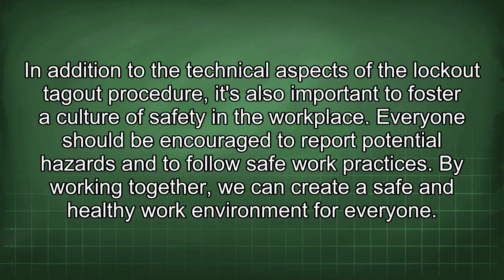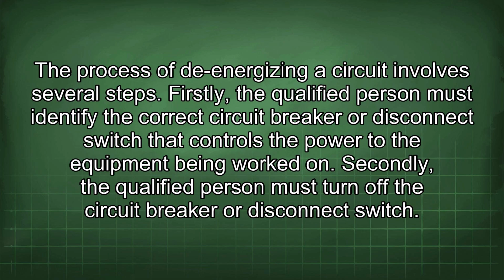In addition to the technical aspects of the lockout tag-out procedure, it's also important to foster a culture of safety in the workplace. Everyone should be encouraged to report potential hazards and to follow safe work practices. By working together, we can create a safe and healthy work environment for everyone. The process of de-energizing a circuit involves several steps. Firstly, the qualified person must identify the correct circuit breaker or disconnect switch that controls the power to the equipment being worked on. Secondly, the qualified person must turn off the circuit breaker or disconnect switch.